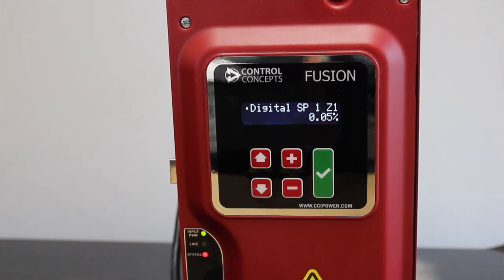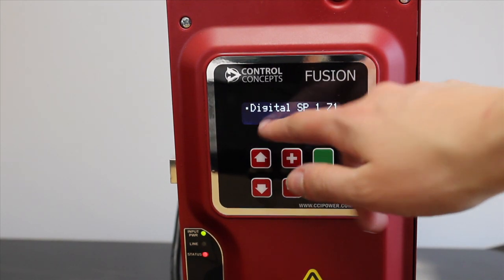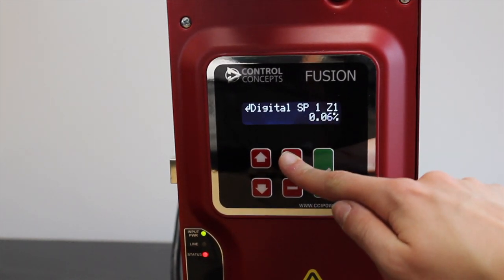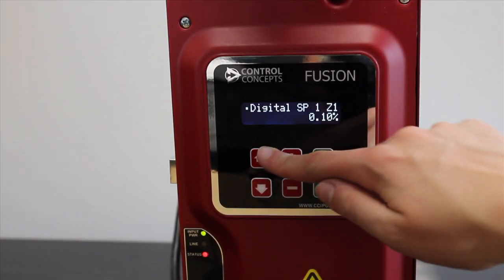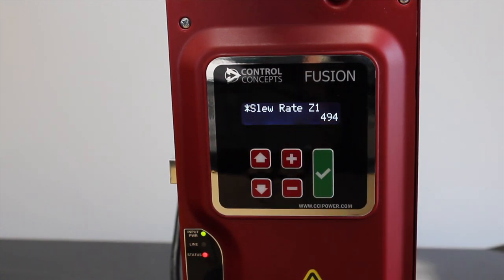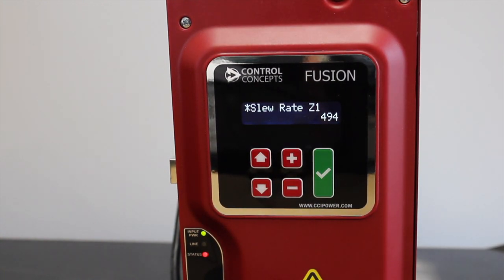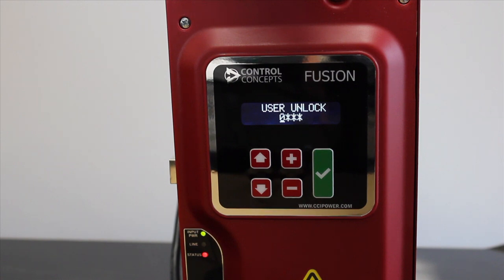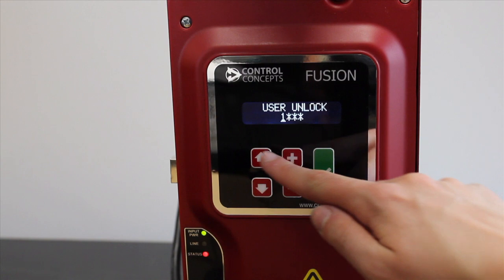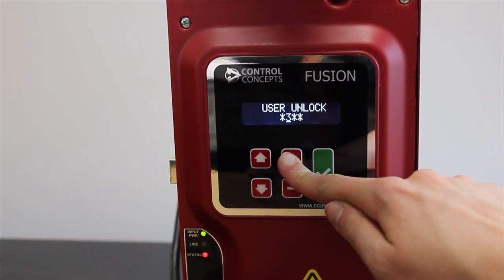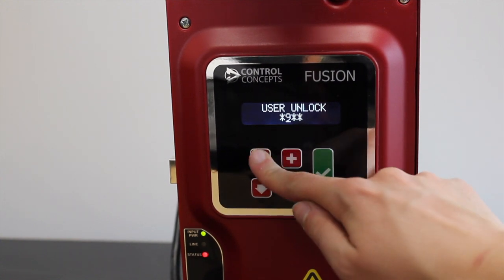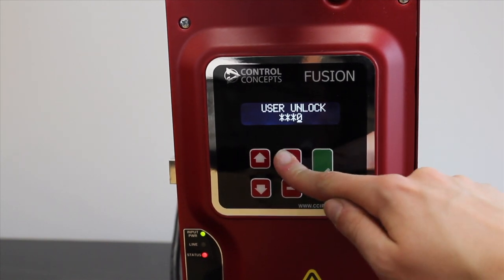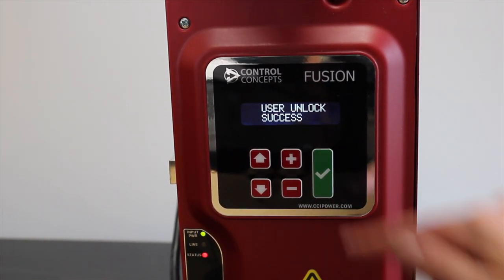An editable parameter will appear on the controller display with a dot preceding the text. Pressing the green checkmark key will allow you to edit the parameter value. When the parameter is locked, an asterisk appears instead, and the green checkmark key will prompt you to enter the password. Use the plus and minus keys to cycle through numbers 1 through 10, and the arrow keys to move back and forth between the four digits. Finally, the green checkmark key will apply the password.